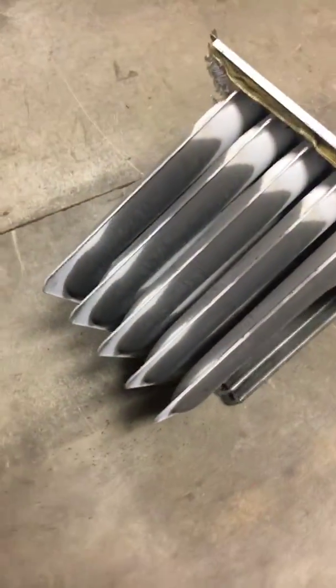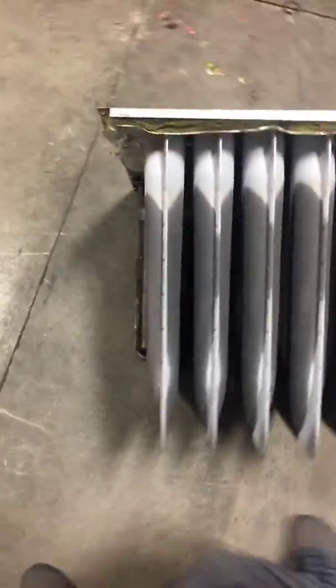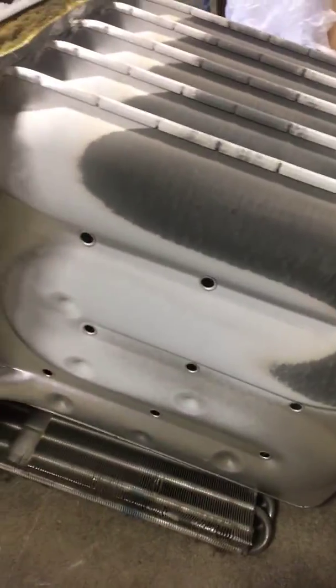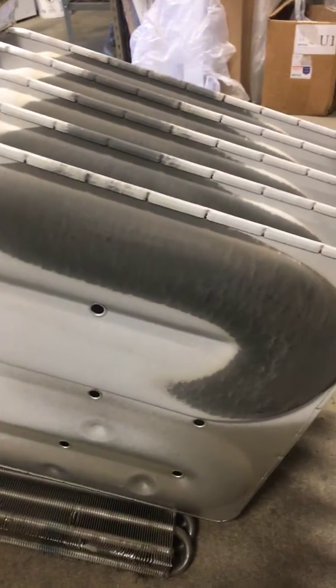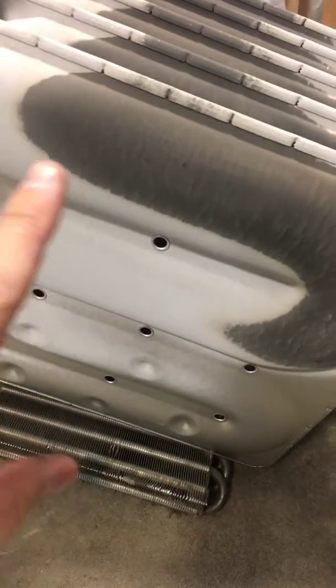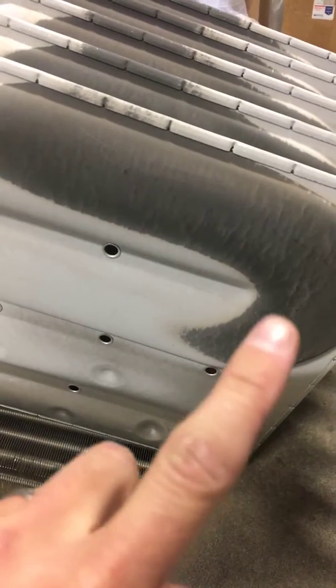One of the things you always want to check for is that a lot of times with 90%ers, you look at the secondary and ignore the primary, but this one in particular, the primary failed. You can really see the heat, see how much heat went through here, and that's where everything was heating up.